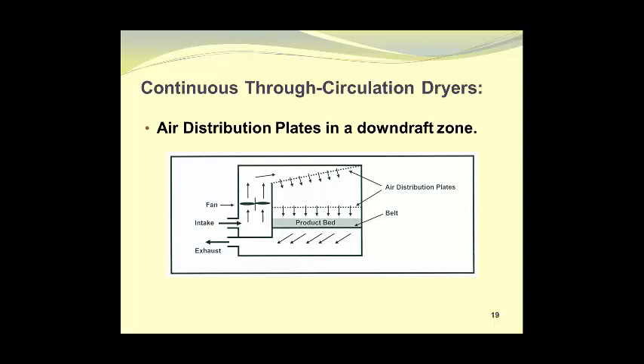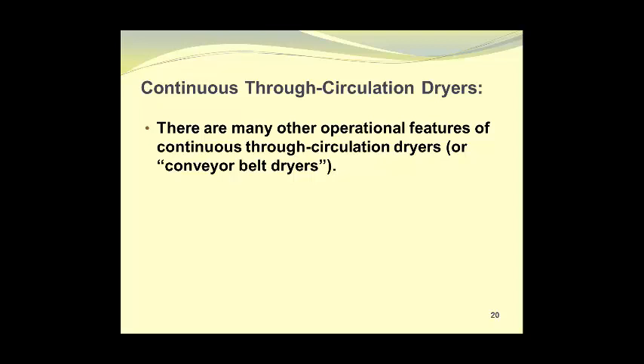In a downdraft zone, the same reasoning applies. However, the air distribution plate is placed above the product, so once again there is a back pressure that creates a nozzle effect for each one of the holes in the air distribution plate. In this diagram, I've actually shown two air distribution plates to even out the air flow even more than when using a single distribution plate. There are many other operational features of continuous through-circulation dryers, or conveyor belt dryers as they are often called, but we will not go into them here.